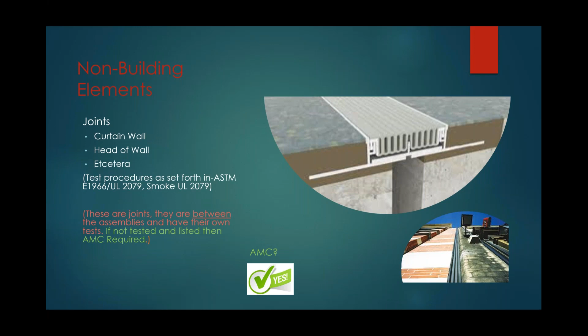Same with penetrations. Penetrations have their own testing requirements and their own test standards. For through penetrations, it's ASTM E814 and UL 1479, and again for the smoke, it's UL 1479. Membrane penetrations are tested similarly. The code has additional allowances for membrane penetrations, but they're tested the same. So again, if you have an EJ for penetrations or membrane penetrations, you will most likely need an AMC for that EJ.